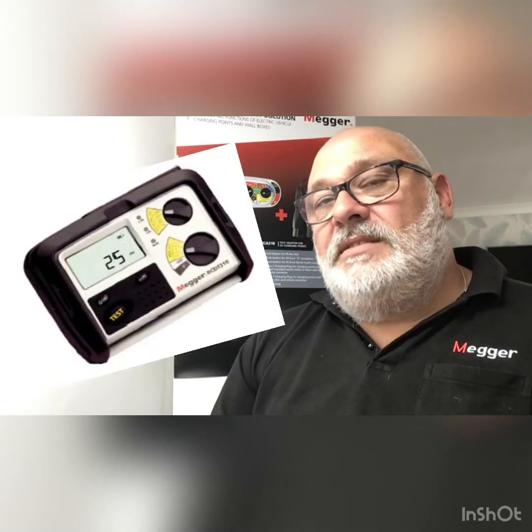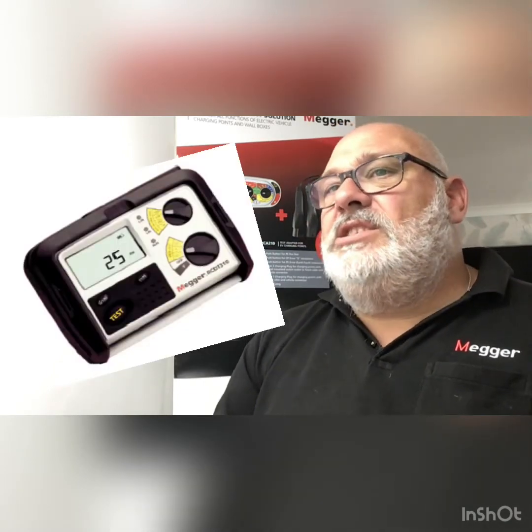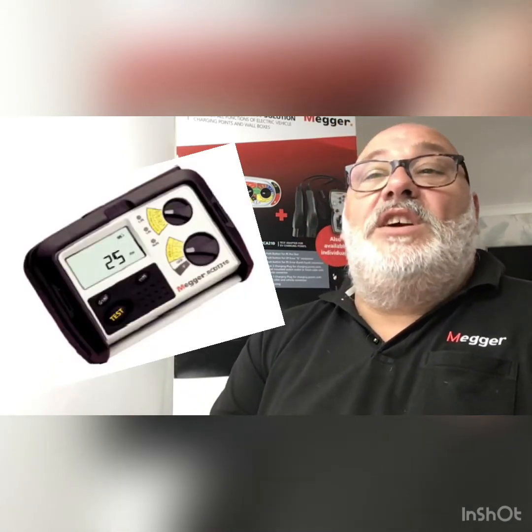That leads us on to the RCD meters. Again, a range of models. These are the RCD 300 series. Now an RCD tester is used to determine the time that it takes for the RCD to trip. The normal tests are carried out at half the rated RCD current, which is half times I, also at the rated current I, and at 5 times the rated current, 5 times I.